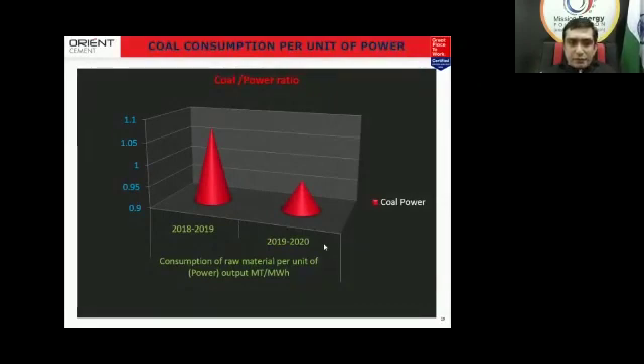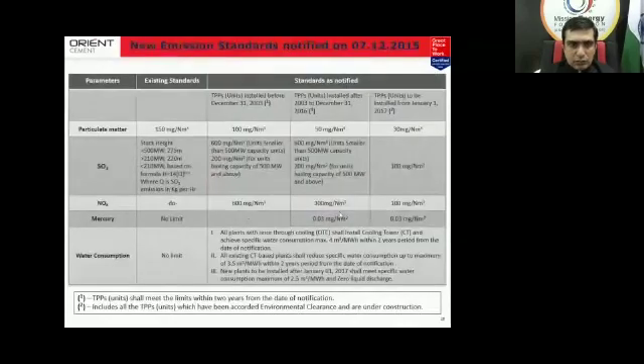So coal to power ratio, sir, is a very common and very important factor in power plants to operate efficiently. Our coal to power ratio was 1.07 MT per MWH in the year 2018-19, which we have subsequently brought down to 0.97, around 0.962. So this has also resulted in a very good result in reducing the net heat rate. So this is just a slide which everybody has shown regarding the new emission standards.